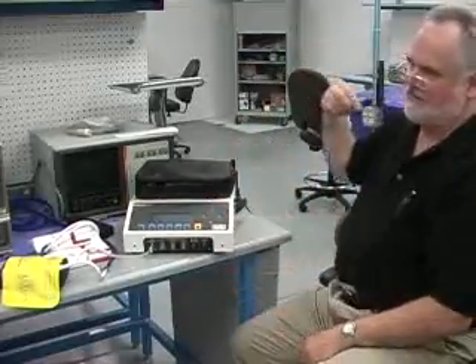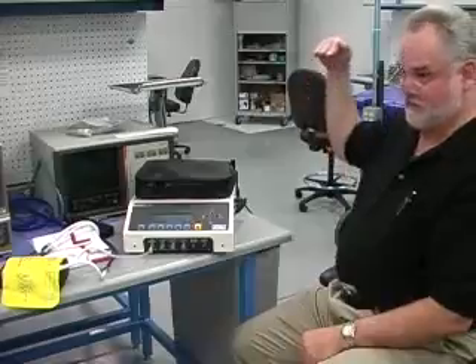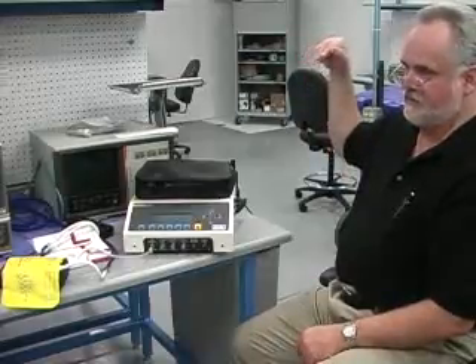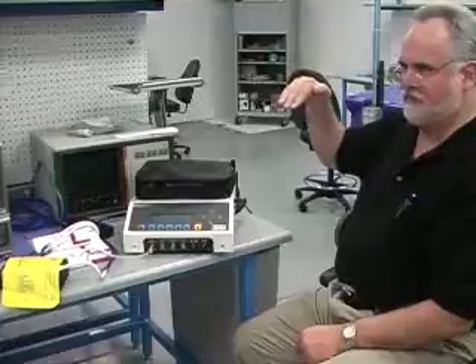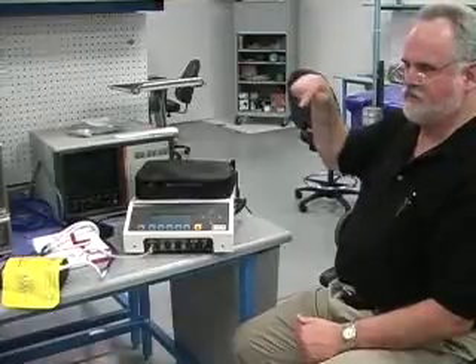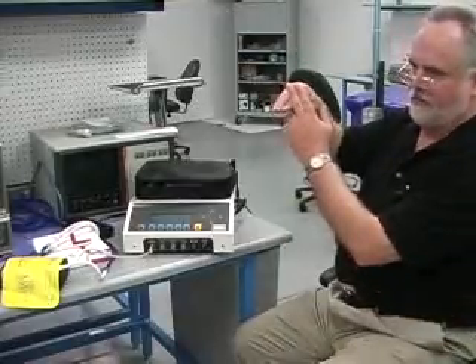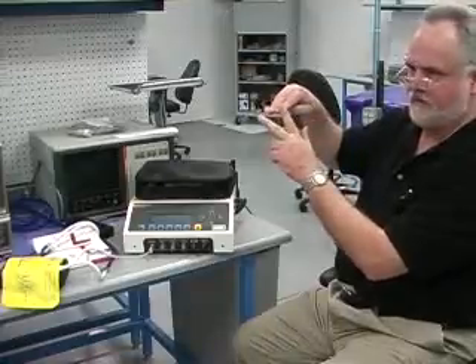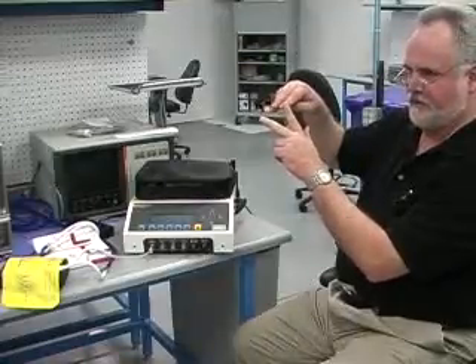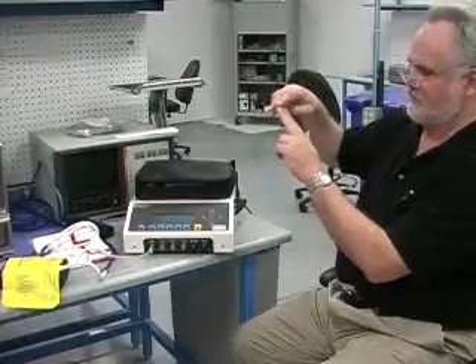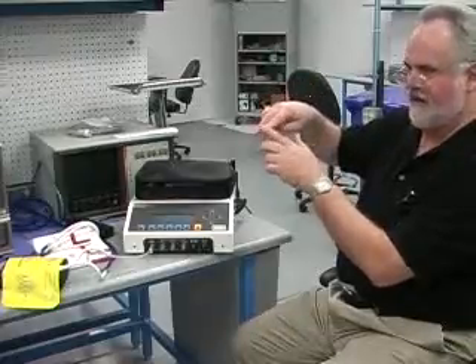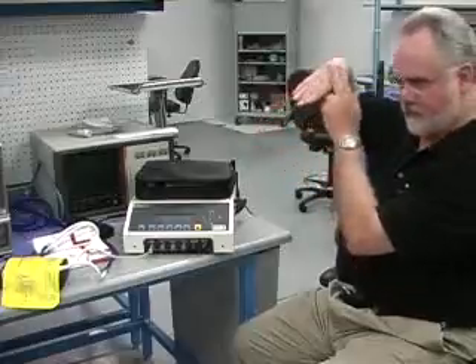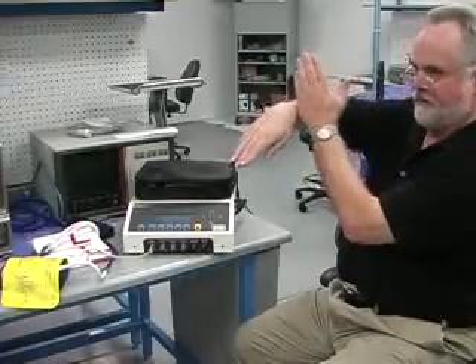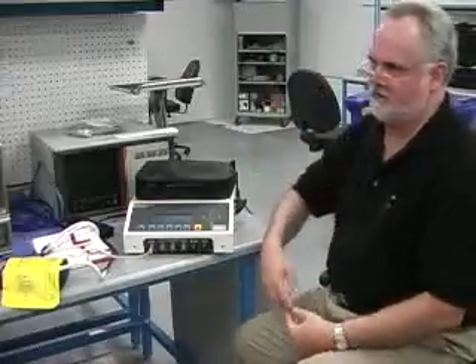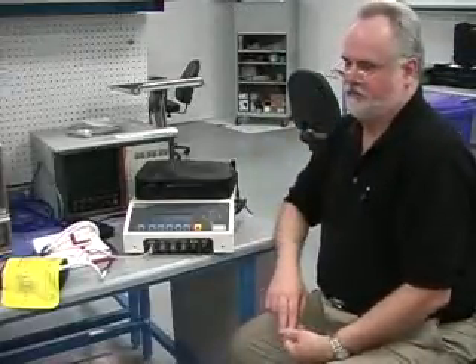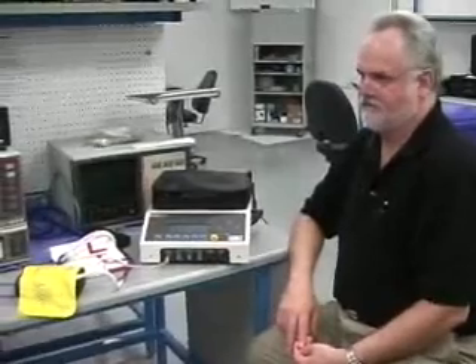We may not be as accurate with those because the pressure is going down a lot faster. We'll measure cuff pressure at one point, but by the time we generate the pulse, the cuff pressure is already going down a couple of millimeters of mercury. So the cuff pressure that we've output is actually referenced back to an earlier, higher cuff pressure, but it's within about 10%. That's typically what you're going to see for these kinds of devices.